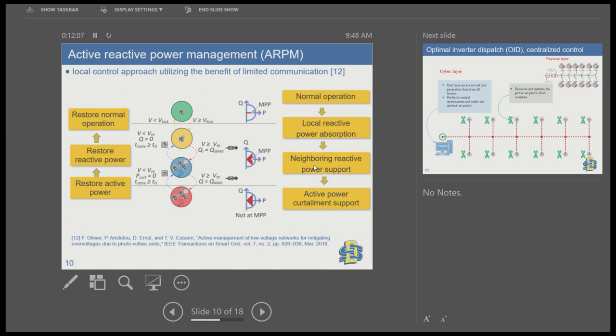Active reactive power management, or ARPM, uses limited communication to coordinate reactive power absorption and active power curtailment. Once an overvoltage occurs, a signal is issued to every PV inverter and they first perform local reactive power absorption. If that is not sufficient, they move to active power curtailment. Once the overvoltage issue is resolved, they restore active and reactive power setpoints to normal operation.